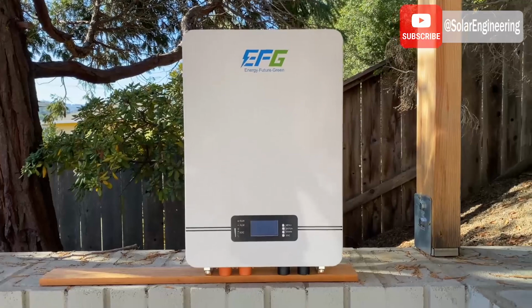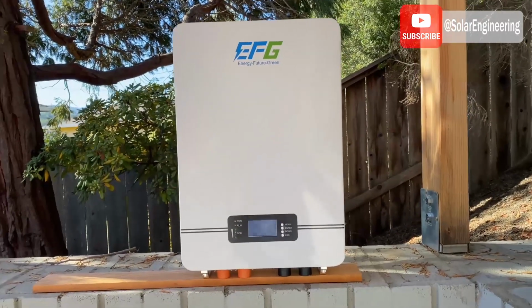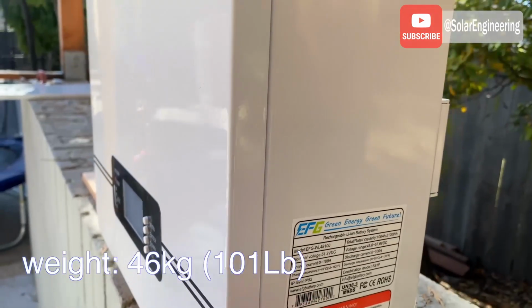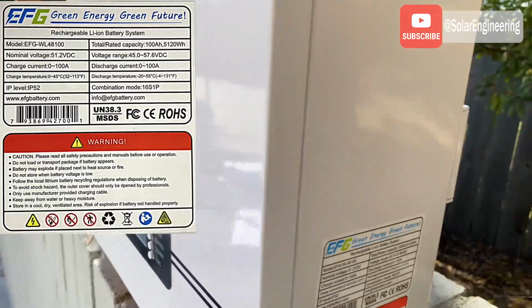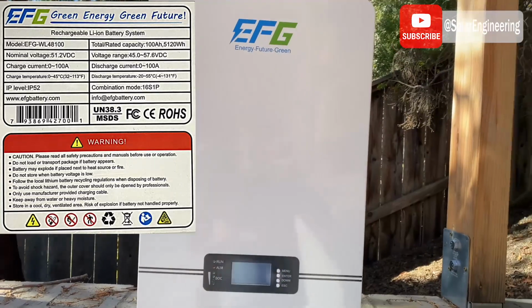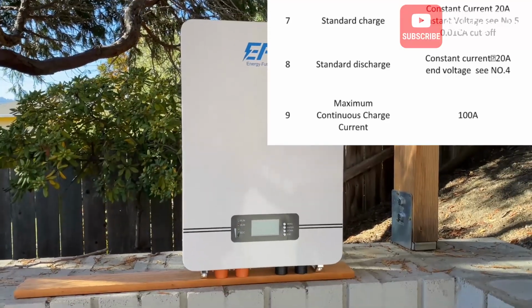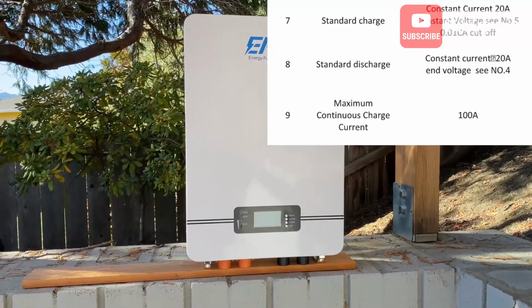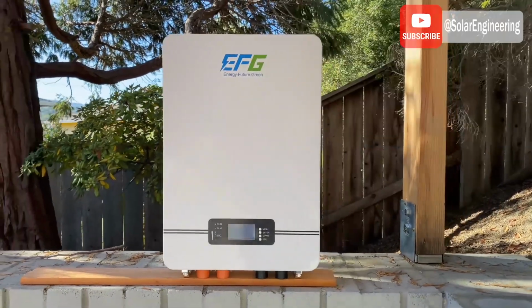The specification for this battery is pretty standard: 51.2 volts, 100 amp hours. On the side we can see the operating temperature and the recommended charge and discharge current at 0.2C, which is 20 amps, with maximum charging and discharge current of 100 amps.